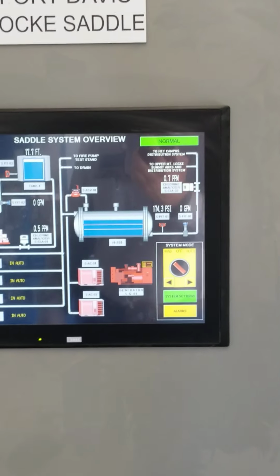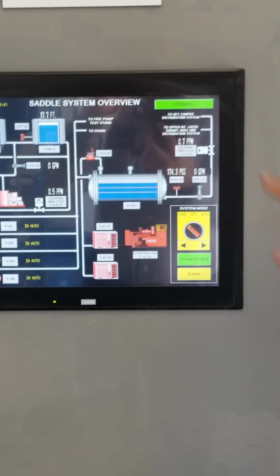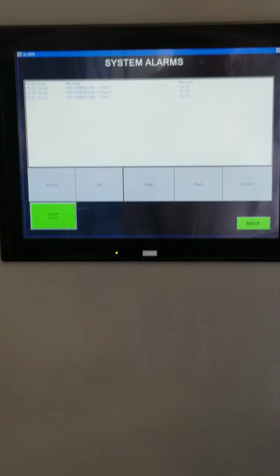Well, when that goes into alarm, that normal button, when you press that, does it give you a drop-down screen? No, it's just an indicator. So it's just an indicator. Yeah, okay. You will go to alarms. Okay, I see. Here's your alarm page. Perfect. So we have a couple of them right now. There's 3 that got stored in there.